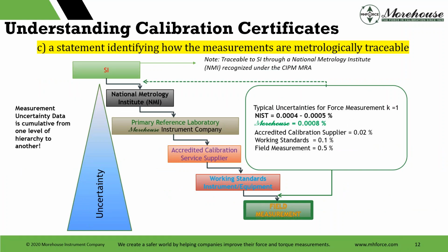And when I say that, I break it down here a little bit differently. So if we look at measurement uncertainty as like a mountain or a pyramid, we start with the SI base units. The measurement uncertainty data is cumulative from one level of the hierarchy to the other. And when using force, the load cell should be calibrated using measurement standards traceable to SI through a National Metrology Institute, NMI, recognized under the CIPM MRA. This recognition is necessary as some NMIs cannot provide traceability.